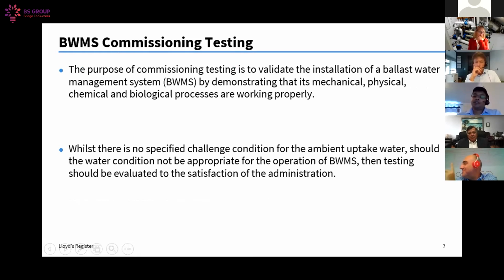Remember the purpose of the commissioning testing: it is to validate the installation, to see whether you have installed the treatment system correctly and whether it operates correctly. This is very clearly mentioned in the Ballast Water Circular 70 commissioning testing guidance. And this commissioning testing is not intended to revalidate the type approval test of a treatment system. The type approval testing is separate. It has been type approved, certified as a unit. What we are doing is that when you bring that unit in different components and install it in your ship in accordance with your layout and the space requirements, we check whether that installation is conducted properly and the system is operating properly.